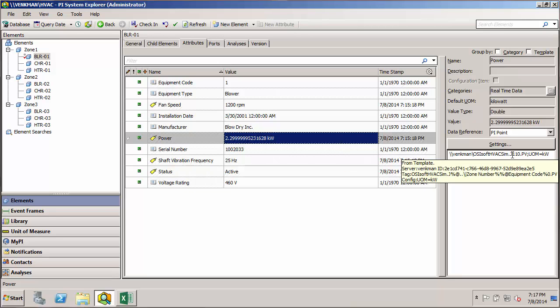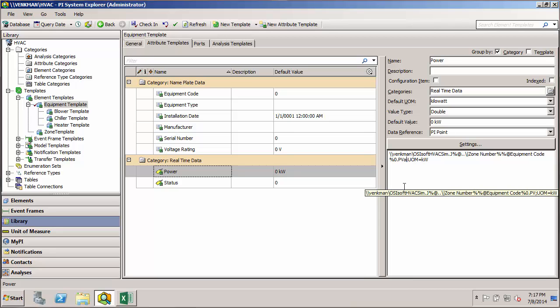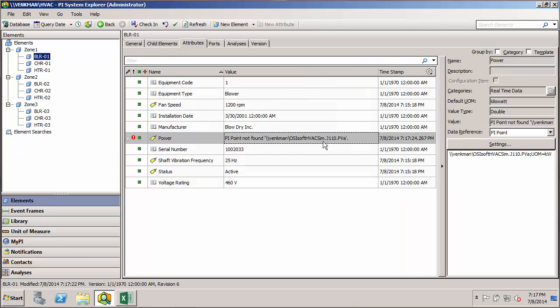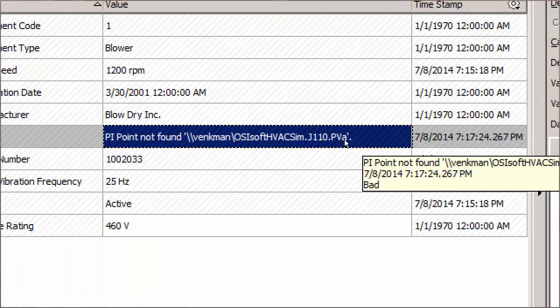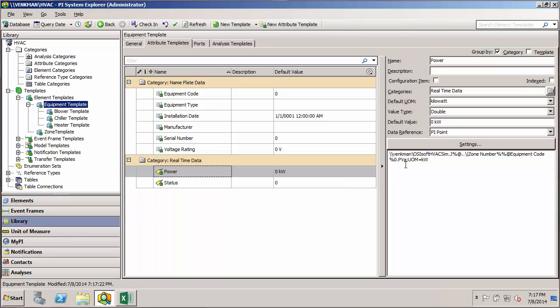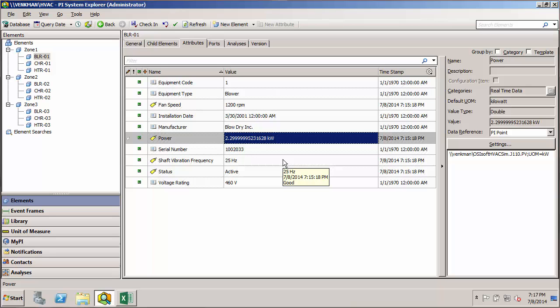To quickly prove it's using the substitution parameters, I'll deliberately corrupt the configuration string by adding a lowercase 'a' to the end of the tag name and check that in. You can see that Power is now not resolving correctly because of that lowercase 'a', which proves it's actually using the configuration string from the template. I'll fix that and check it back in — and now we can see everything is working fine with our Power attribute.